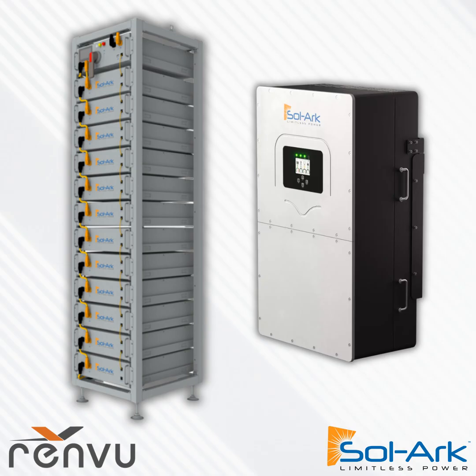I don't think even luxury homes need more than an 80 kilowatt hour battery bank, and that could be done with two 40 kilowatt hour stacks of Renon batteries right in front of a Sol-Ark 15K without any combiner block. We're so spoiled now with a plethora of design configurations that I think 48 volt is the right selection for residential, because with residential you have so many curious hands and eyes around these systems, and 48 volt is less likely to jump out and grab you - so safety comes into play.